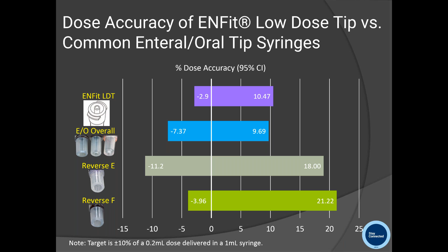And so you see the ENFit low-dose tip and the enteral oral were statistically similar in terms of their dose accuracy, versus 2 other reverse orientation systems. One is a proprietary system by a company called Vizient that is out there in use today, and another is a reverse system that's used in the United Kingdom today and available by many manufacturers. And both, we found, offer dose accuracy that is worse than what's expected, greater than the plus or minus 10% error range that pharmacists and physicians and nurses would expect to see. And so what we found is that the ENFit low-dose tip was considered to be equivalent to enteral and oral use syringes today, and we believe it is going to allow for delivery of an accurate dose.